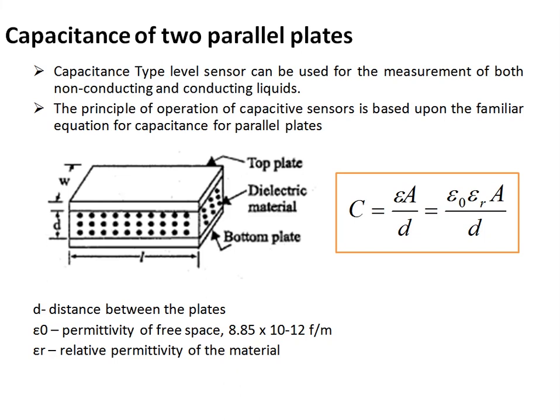εᵣ is the relative permittivity of the material, also known as the dielectric constant. A is the area of the plate and d is the distance between the plates. By varying any of these parameters — dielectric constant, area, or plate separation — the capacitance changes, and by measuring capacitance, these variations can be detected. This type of capacitor-based level sensor can be used for both conducting and non-conducting liquids.